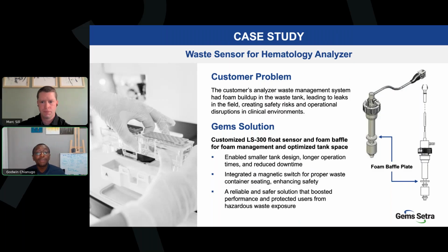This is a real-world example of how Gems Setra helped solve a common challenge in hematology analyzers. A hematology analyzer is a medical lab instrument used to analyze blood samples, specifically to count or characterize blood cells such as red blood cells, white blood cells, and platelets. In this case, the customer was experiencing issues with the waste management system inside the analyzer.